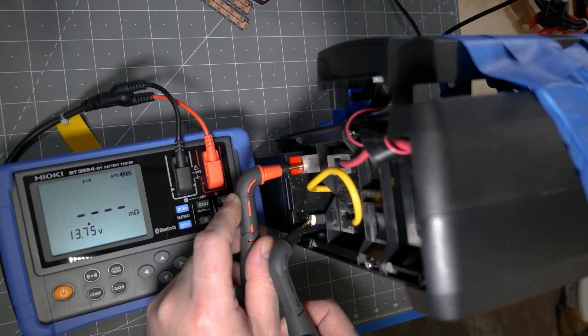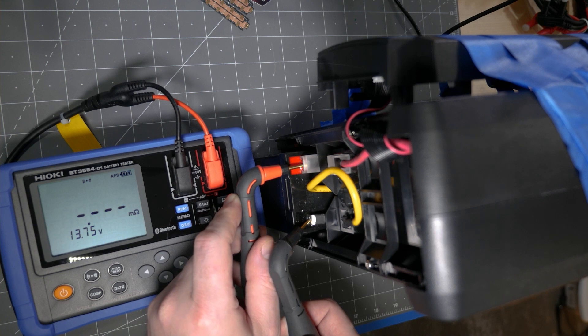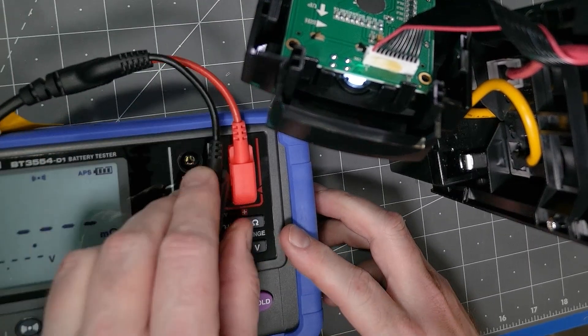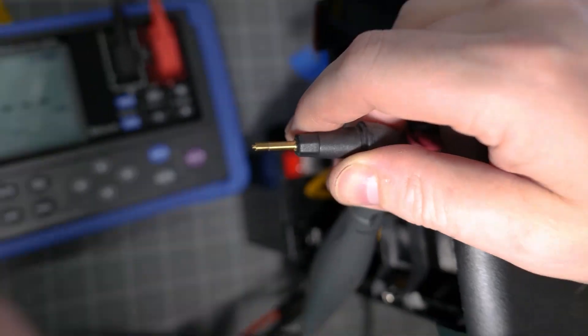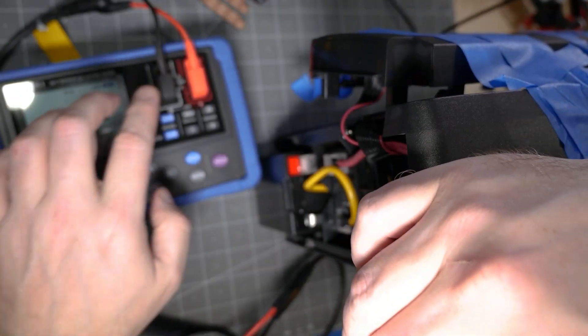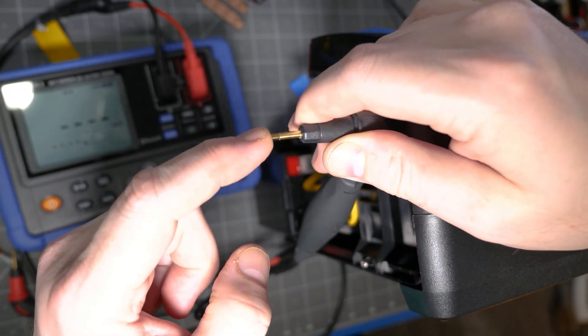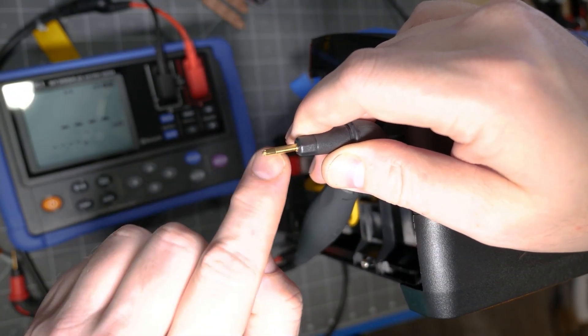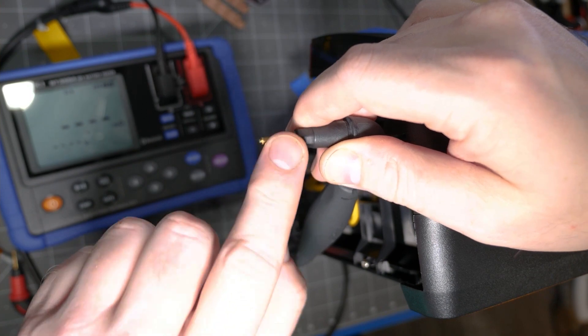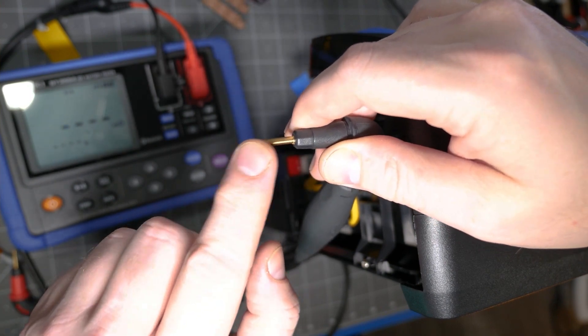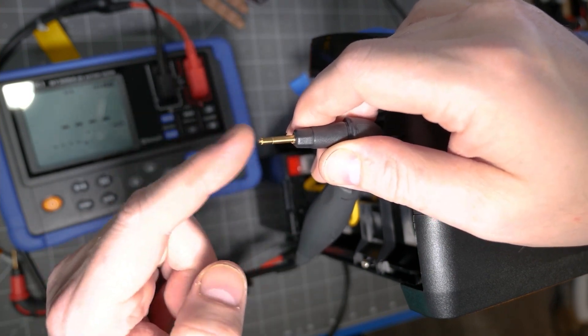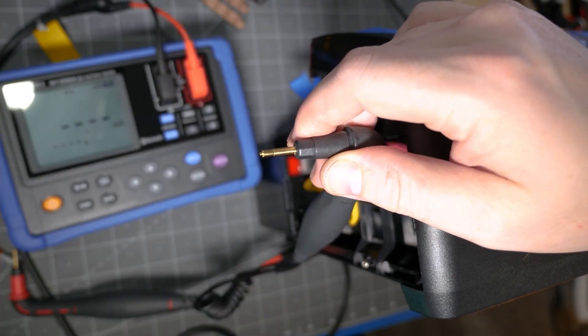Now, sometimes on the meter, I saw a voltage measurement, but not an ESR. It turns out the probes are like a Kelvin or 4-wire connection. And when I looked close at the probes, there is a crown tip and a sheath. If both do not make contact to the terminal, you do not get both measurements.